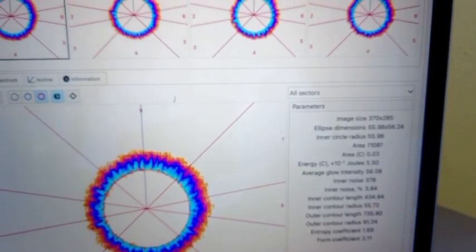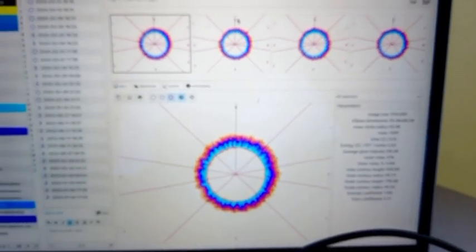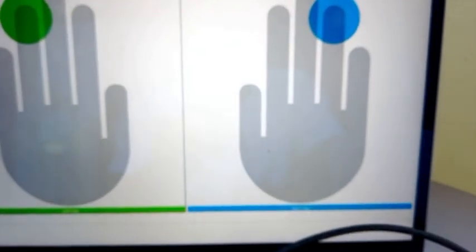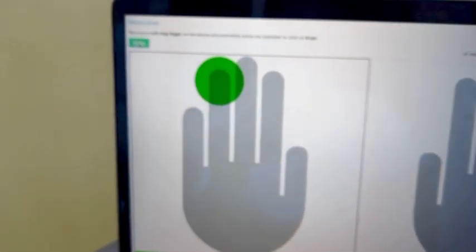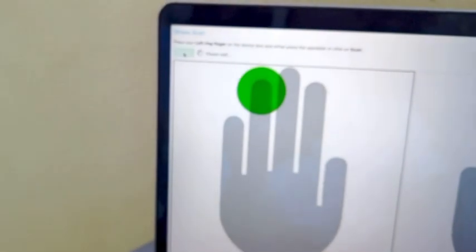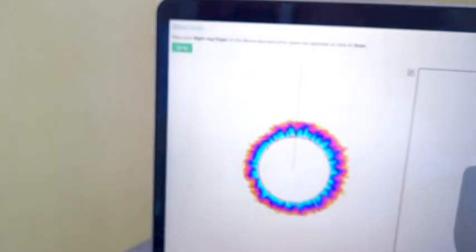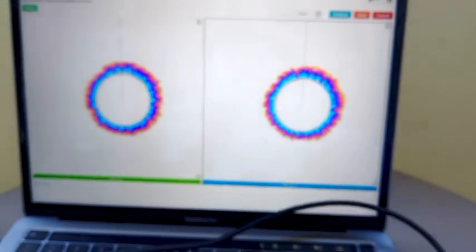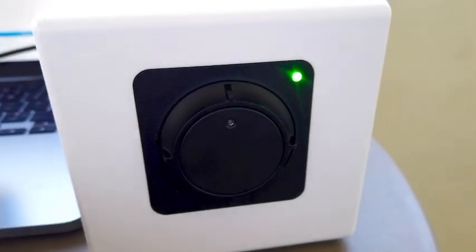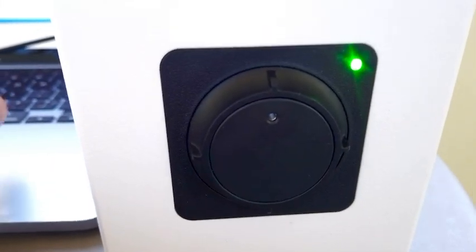Now to even further test that, you can go to your stress scan and then do a stress scan. So we come here, click on Scan, and then again - now I'm just doing this with the calibration device already inserted there, I'm not changing anything.